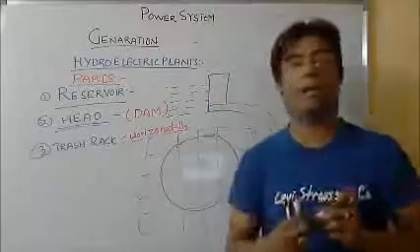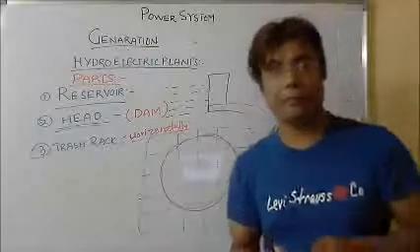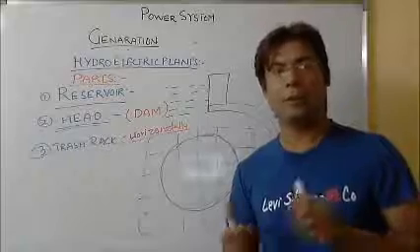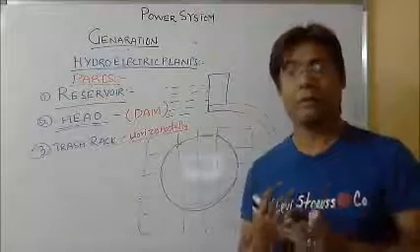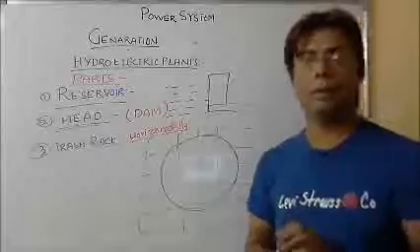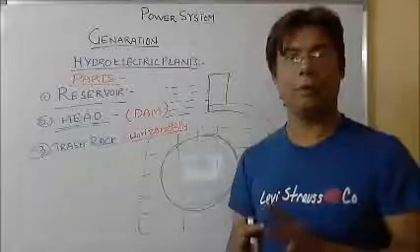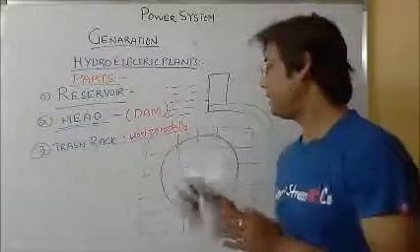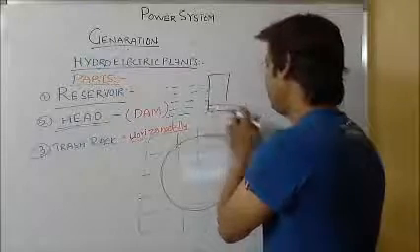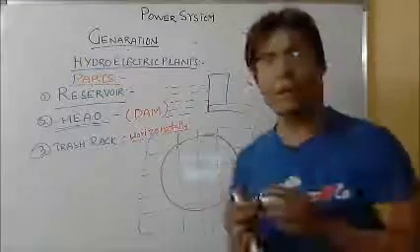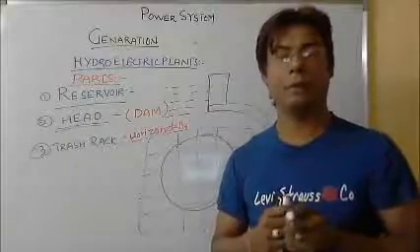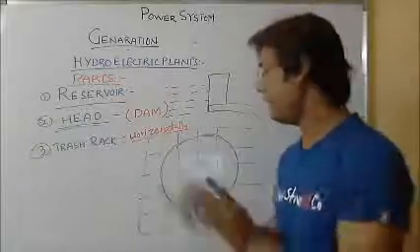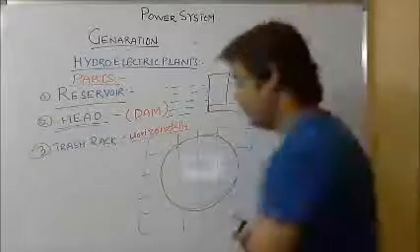such that no wastage, any polythene or similar material, will restrict flow or cause blockage by blocking the turbine nozzles. Anything which is not required apart from water will not be able to pass this and come into it. So this is a trash rack, which restricts debris material from entering the penstock. Trash rack is very important and they are used horizontally. Please remember that.